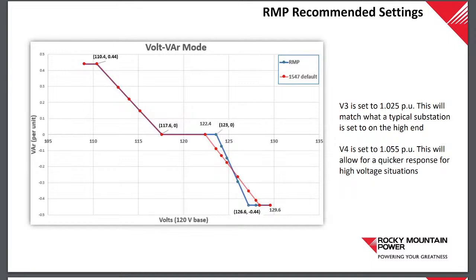And then, if you follow the blue line down to 126.6, we're going to get to full support of that voltage regulation a little bit sooner than the IEEE recommended default settings, and that's just to get a quicker response when we're having some overvoltage. So we want to get our voltage down a little bit quicker than the default settings, and again, that's still within the settings to do that.